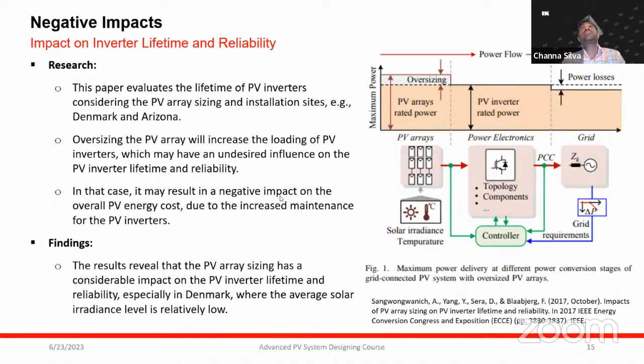In most cases we have seen that with very small-scale inverters, the majority represent probably around 20% oversizing. But when it comes to larger-scale central inverters, they can easily oversize more than 50%. The inverter allows that. But in some cases there are restrictions from the voltage or current perspective, and maybe some don't provide an efficiency curve or consideration. In such a case, if you oversize, that may directly negatively impact the lifetime and the reliability.